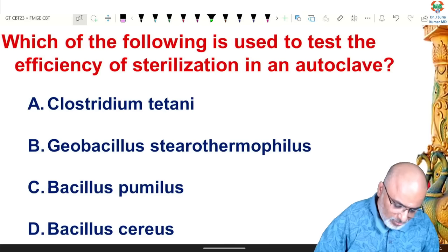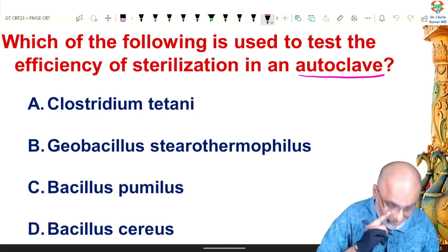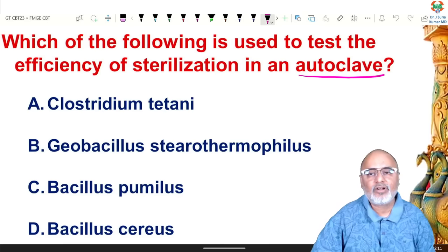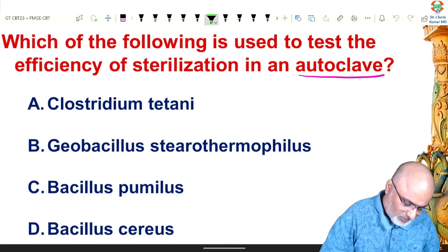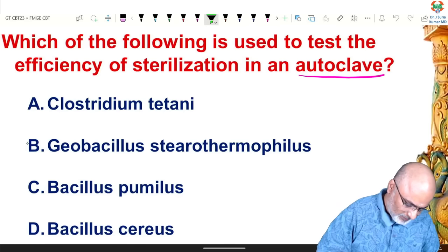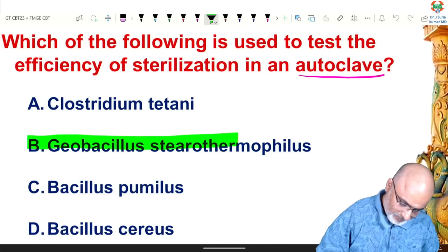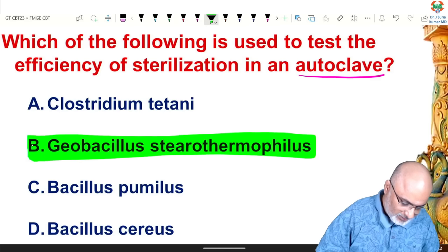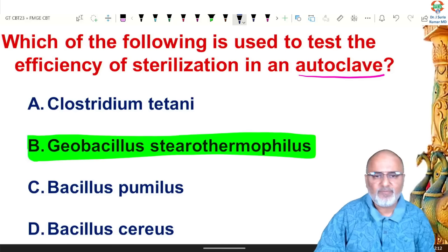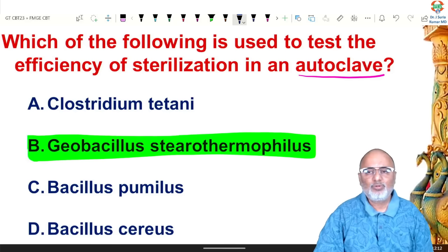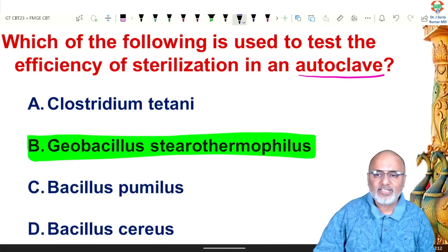For autoclave, the quality control agent is Geobacillus stearothermophilus. The spores of Geobacillus stearothermophilus are used as a quality control agent for autoclave.